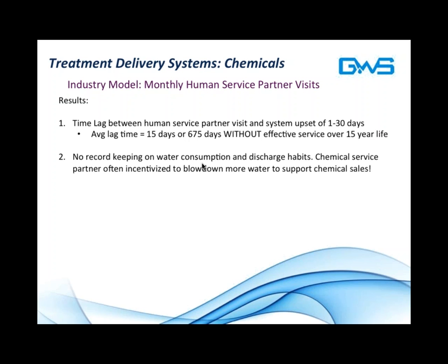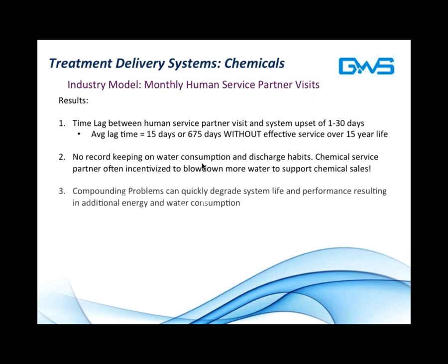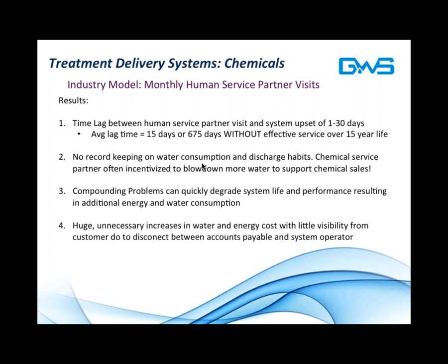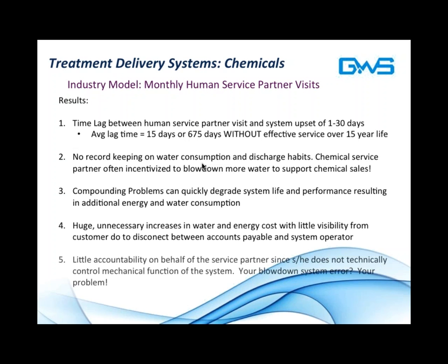There's no record keeping on water consumption and discharge habits because monitoring that becomes expensive. Chemical service partners are often incentivized to blow down more water to support chemical sales. So this flies in the face of what the goals of the owner-operator are in terms of water savings. Compounded problems can quickly degrade system life. As I mentioned, the example of a problem occurring downstream on January 1 and the tower sitting uncontrolled for 29 days until the service partner returns to visit. And then huge unnecessary increases in water and energy costs with little visibility from the customer create a disconnect between accounts payable and a system operator.